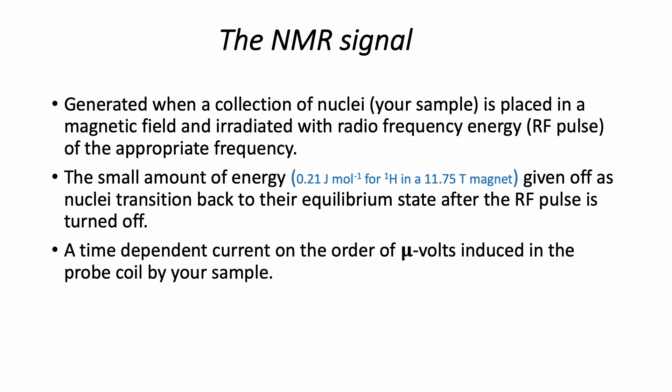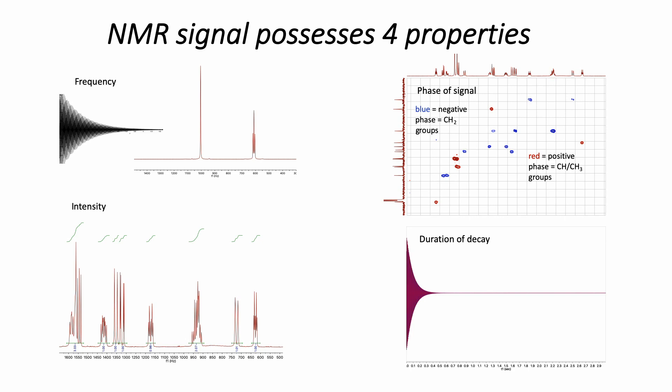The NMR signal is generated when a collection of nuclei placed in a strong magnetic field is irradiated with radio frequency energy of the appropriate frequency. The signal is a very small amount of energy given off as the nuclei transition back to their equilibrium state — a time-dependent current induced in the coil on the order of microvolts. An actual NMR signal is called a free induction decay; it's a damped sinusoid with four properties we make use of.